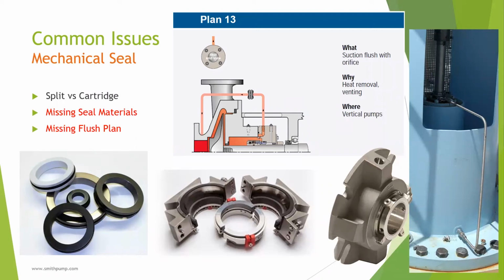Mechanical seals have become popular over traditional packing, but sometimes major details are missing, such as the type of seal or materials of construction, or even the seal flush plan. Turbine seals come in two main flavors, cartridge and split. Cartridge seals are known for their reliability and leak-free design. However, split seals are gaining popularity for their ease of replacement. Remember to specify seal face materials suitable for the application. Typically, soft faces are used for clean water and hard faces for dirty water.